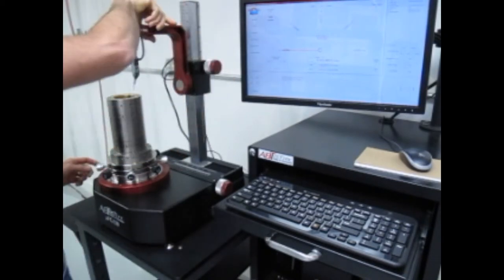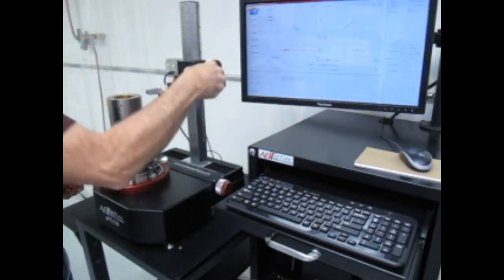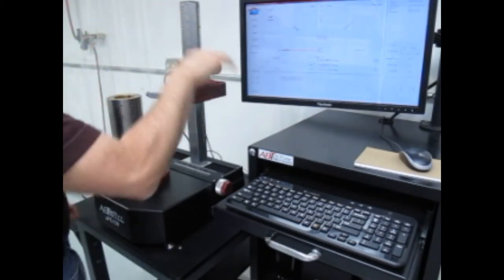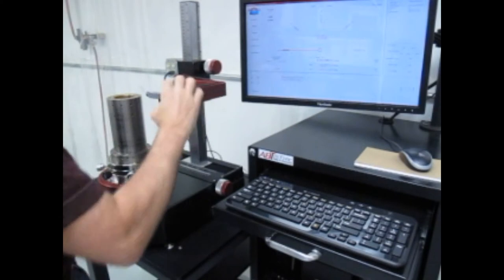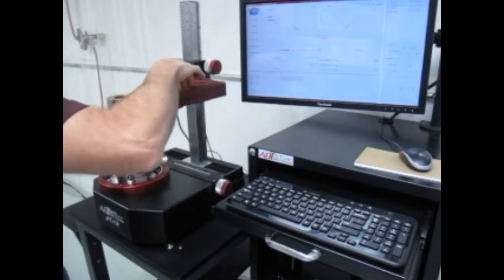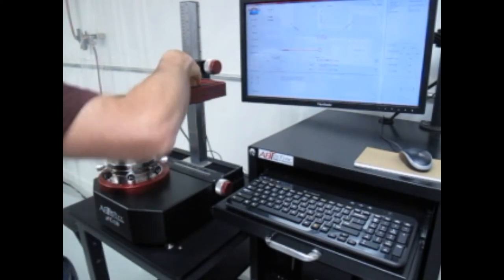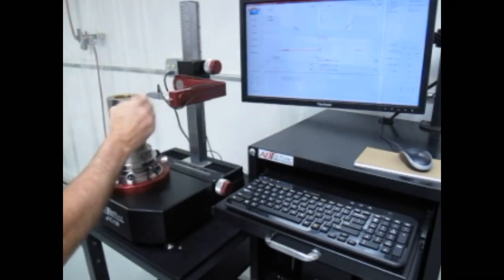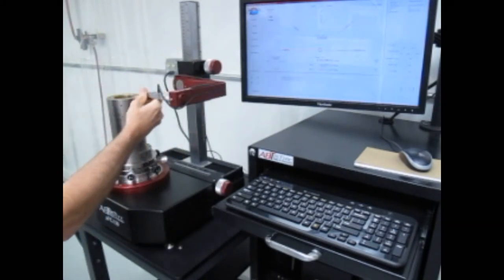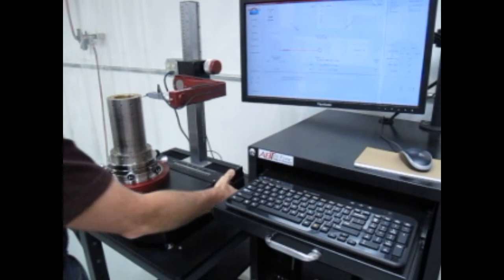And I'm going to articulate the gauge stand down to the 90 degree detent horizontal, rotate the position of the probe head.